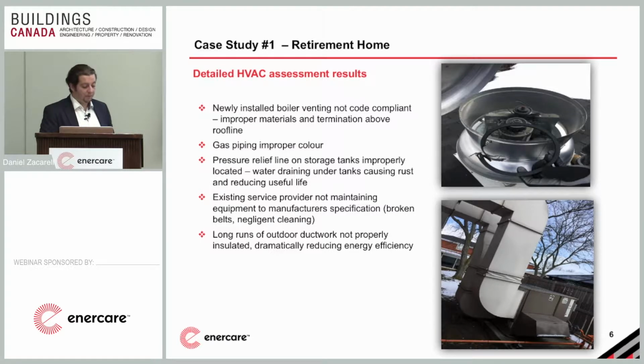Another thing is the pressure reliefs on these storage tanks. Every now and then pressure reliefs go and a little bit of water comes out. They're supposed to be piped in a direction towards the slope into the drain. If it's piped at the back of the storage tank, for example, and the slope goes underneath it, you can imagine that water is going to flow underneath your storage tank and get stagnant every now and then.